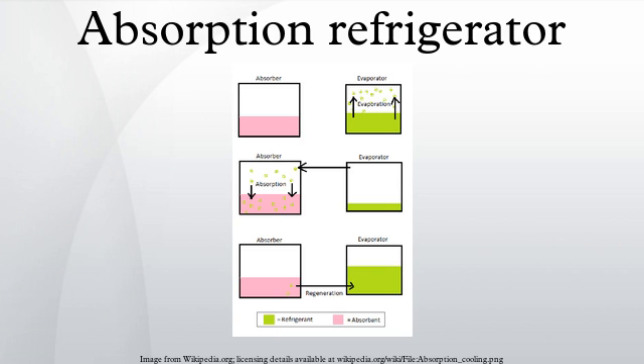The salt solution is regenerated by heating it under low pressure, causing water to evaporate. The water evaporated from the salt solution is re-condensed and re-routed back to the evaporative cooler.